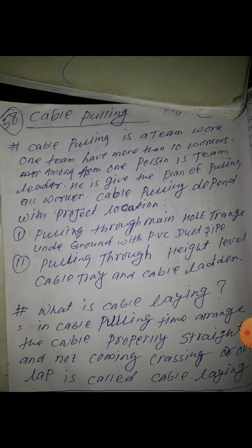During cable pulling, you should not make the cable lapping, overlap, or crossing - that should be clear. One cable tray inside has minimum 6, 7, 8 pieces of cable going there, so you can check all cables are going straight, not overlapping, not crossing. If there is any crossing, this is not accepted and will not pass with the consultant.